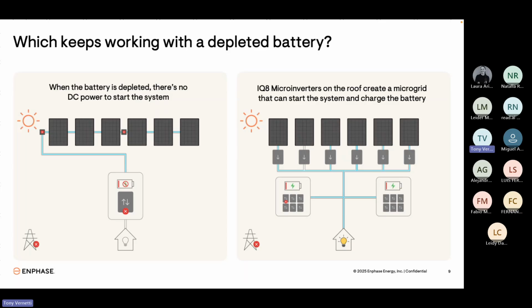And the reason is something special about our microinverters on the solar panels. Our microinverters on the solar panels don't need a working battery to actually wake up and start producing power if the system is disconnected from the grid. They have what's called grid forming capability. So they can produce backup power even without the battery for a period of time in order to get that battery system automatically restarted.